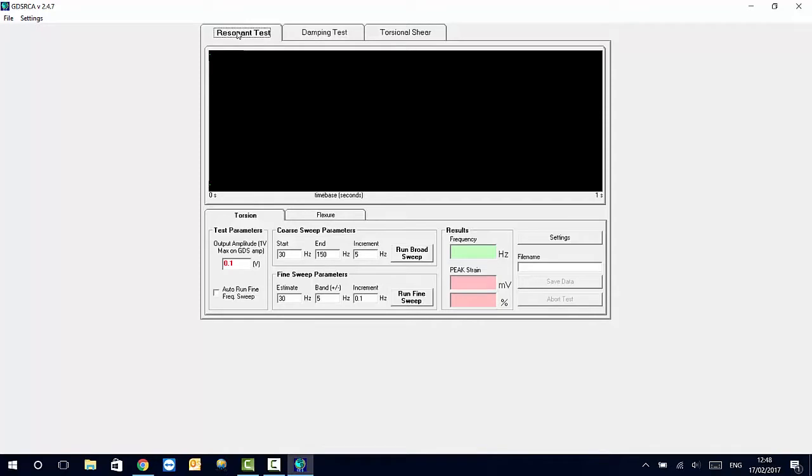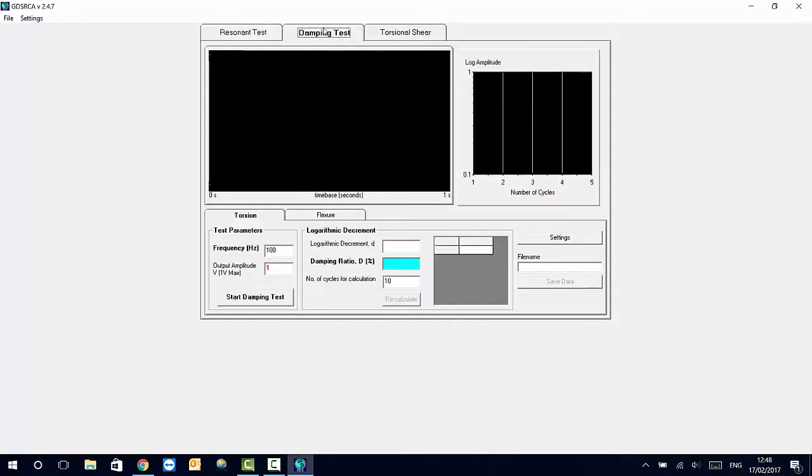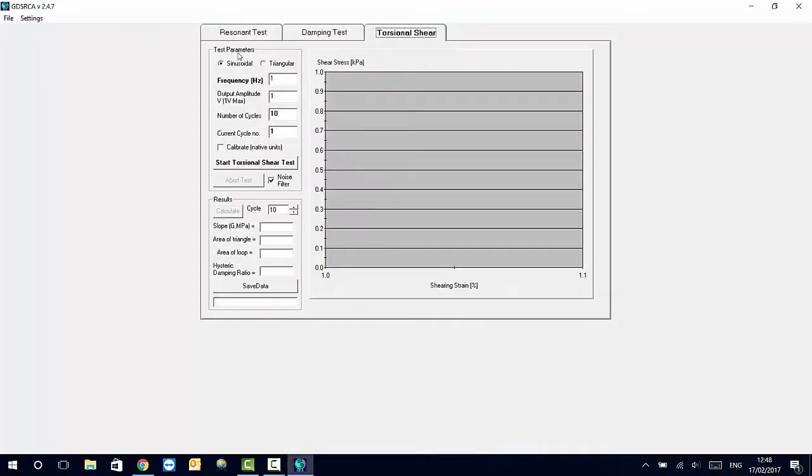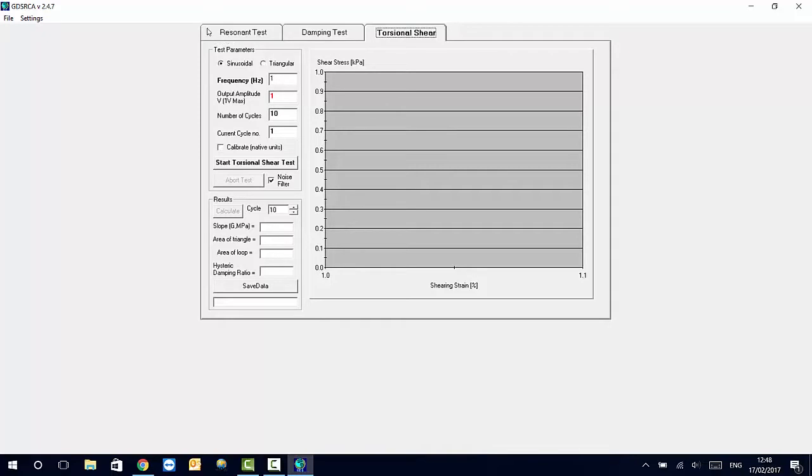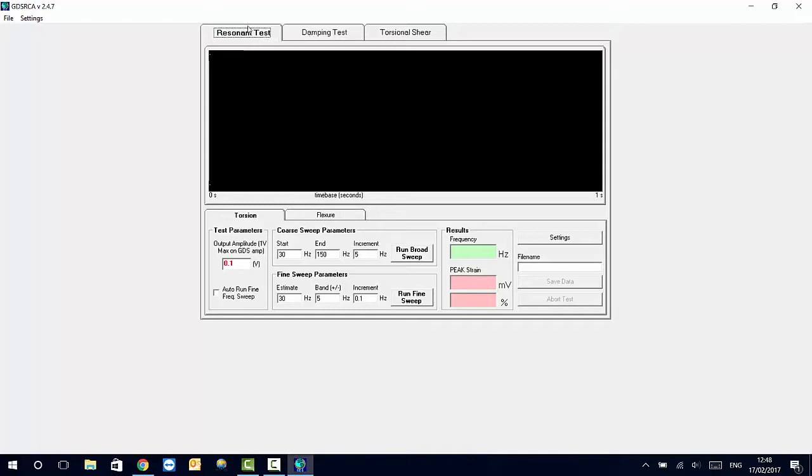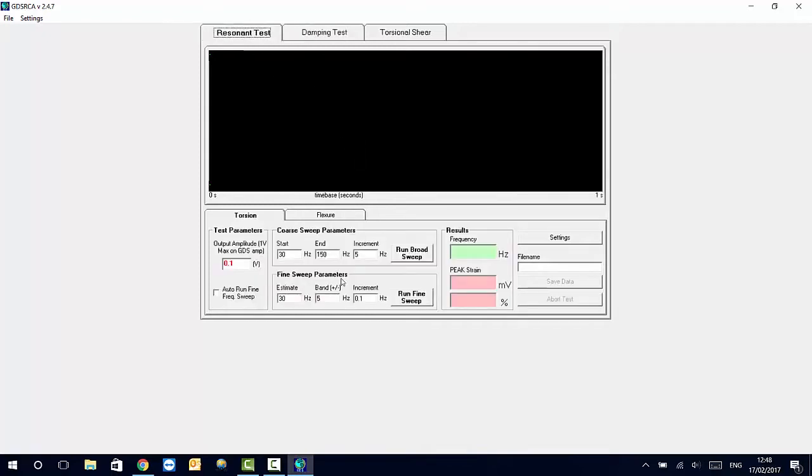Here we can run resonant testing, damping testing and torsional shear testing depending on the upgrade and version of the machine that you have. The basic system will allow you to run resonant tests and damping tests and the main window will allow you to select the ranges of frequencies that you want to cover in order to find the natural frequency of the sample.